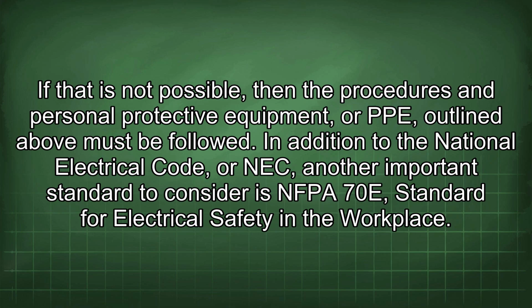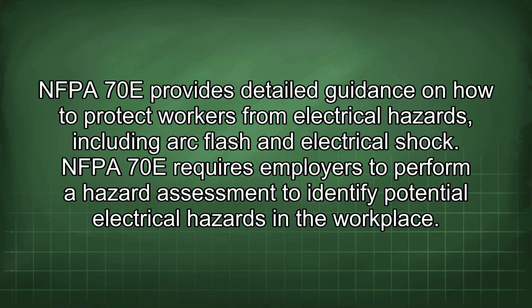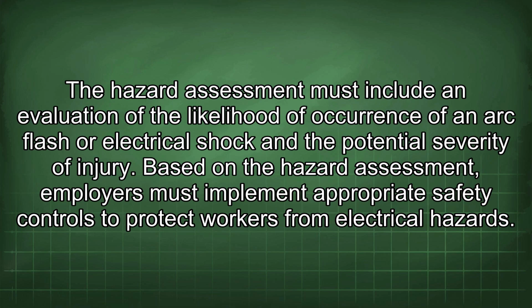In addition to the National Electrical Code, or NEC, another important standard to consider is NFPA 70E, Standard for Electrical Safety in the Workplace. NFPA 70E provides detailed guidance on how to protect workers from electrical hazards, including arc flash and electrical shock. NFPA 70E requires employers to perform a hazard assessment to identify potential electrical hazards in the workplace. The hazard assessment must include an evaluation of the likelihood of occurrence of an arc flash or electrical shock and the potential severity of injury.